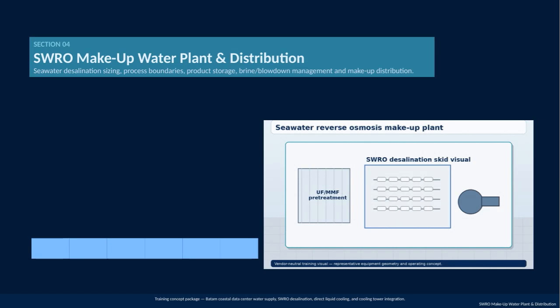Now we'll focus on the SWRO makeup water plant and distribution, which is a critical part of our water supply system for the Batam Coastal Data Center. Here, we'll dive into several key aspects. First, we'll look at how we size the seawater reverse osmosis desalination system to meet the facility's needs. Then, we'll define the process boundaries, which means understanding where the desalination process starts and ends in the overall water system. We'll also cover how the purified product water is stored after treatment and discuss strategies for managing the brine and blowdown byproducts to minimize environmental impact.